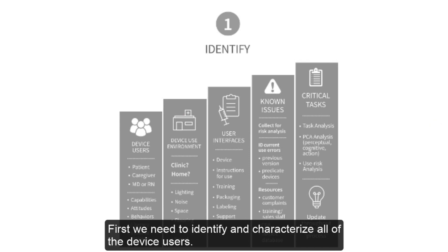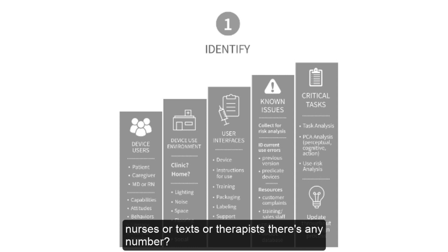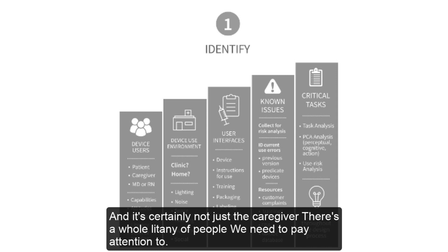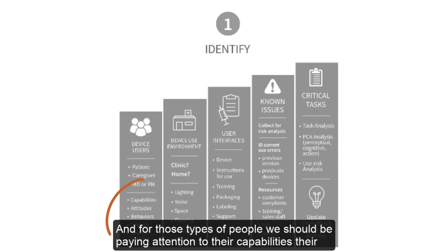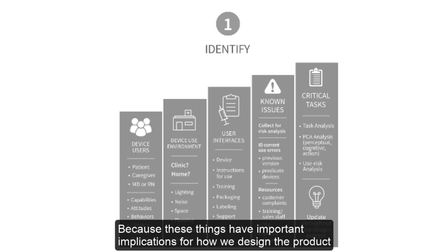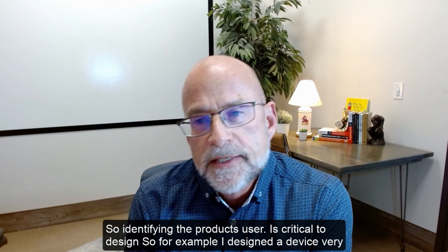First, we need to identify and characterize all of the device users. Are they patients? Are they caregivers? Are they physicians, nurses, techs, or therapists? There's any number of people who may be end users. For those types of people, we should pay attention to their capabilities, attitudes, behaviors, literacy, and even their level of training, because these things have important implications for how we design the product and at what level we assume knowledge. Identifying the product's users is critical to design.